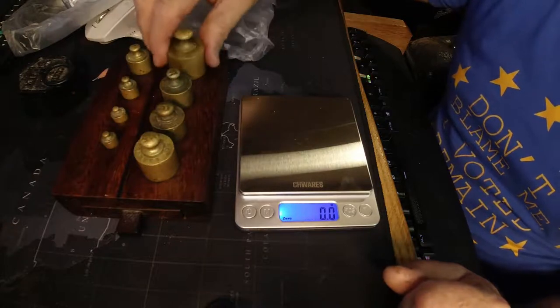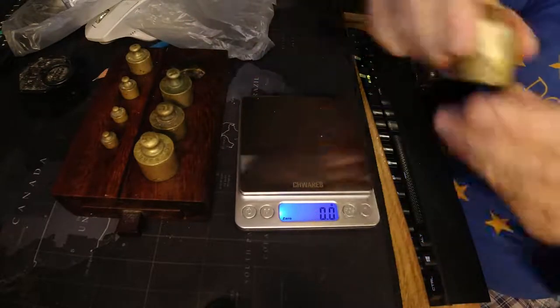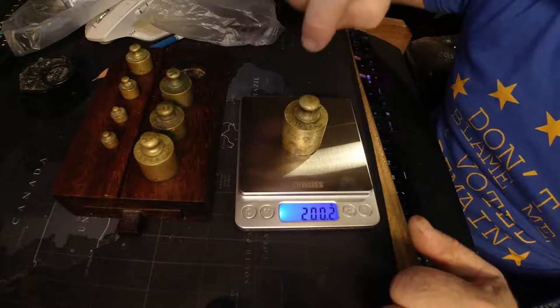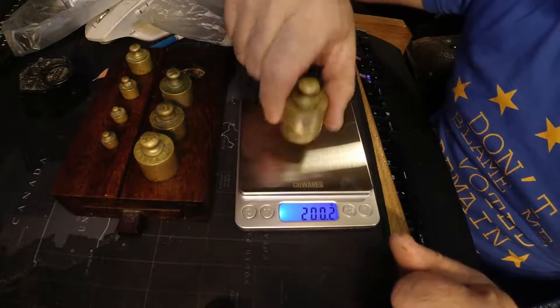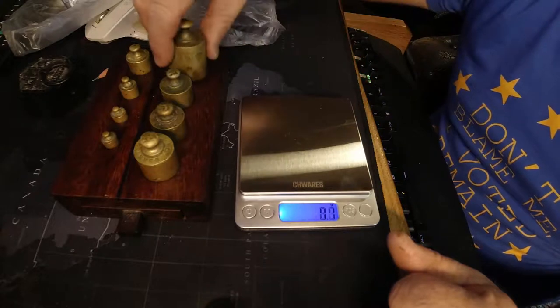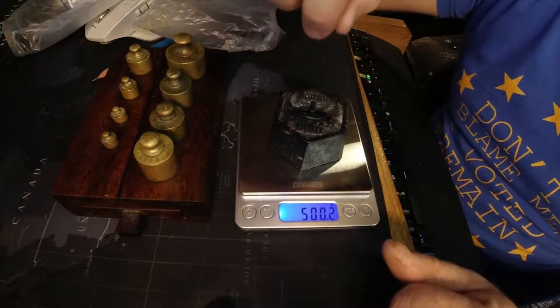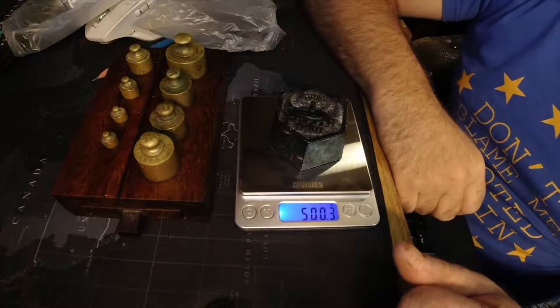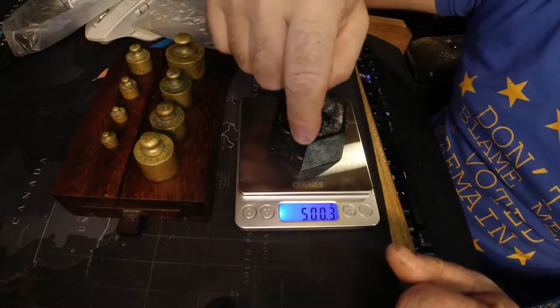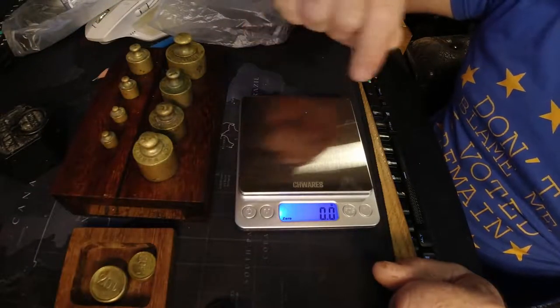And now we're going to go up to the 200 grams. Ooh - might have been on the heavy side, it's always got stuff stuck to it. So it's 0.2 of a gram heavy according to this. I think the weight is heavy, not the actual scales - because the other weights seem to have been pretty accurate. Now I'm going to jump up to 500 grams. And that's 500 grams - how accurate is that? For an iron weight like that, that isn't bad. 0.3 of a gram out. For that type of weight I'm not worried - that is pretty good. So so far so good, I'm quite convinced that these actual scales work very well.